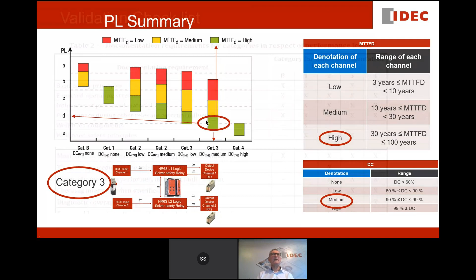So you can get the same performance level using a category 2 architecture and a medium diagnostic coverage and high MTTFD. You could even do it with medium MTTFD and low diagnostics with your category 3 architecture. So you use this table to choose which you're going to do. We've selected category 3 architecture with high and medium on the DC and the MTTFD. And now we can safely say that if we follow what we've designed there, we will have achieved performance level D.